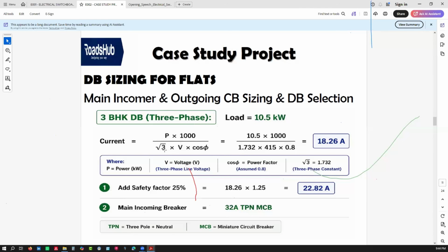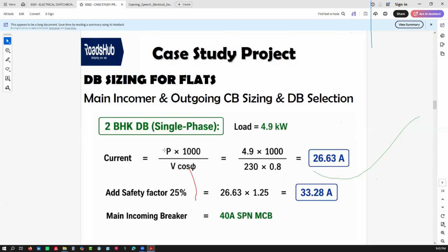That is 25% extra. So you get 22.82, and that's not in the market. Depending on the range that is in the market, some of them we can get at 25 amps if there is, but you can work with 32. Okay. So you need a 32 amp TPN MCB, but this other one, you needed a 40 amp SPN MCB. So these are specific breakers that will be supplied by the SMDBs, because these are actually DBs that are very close to your loads.